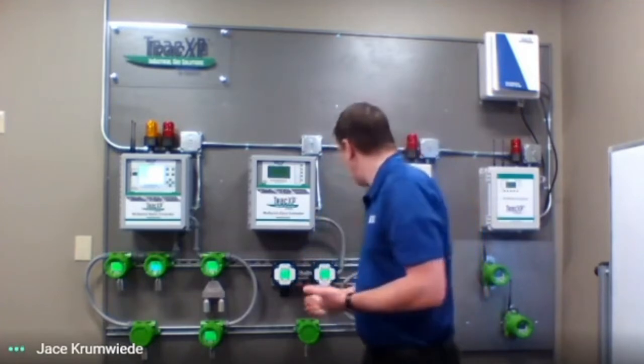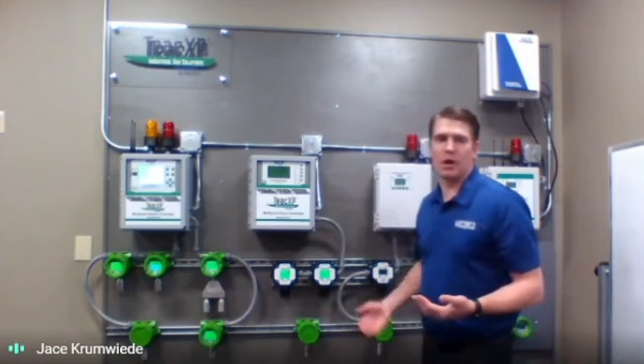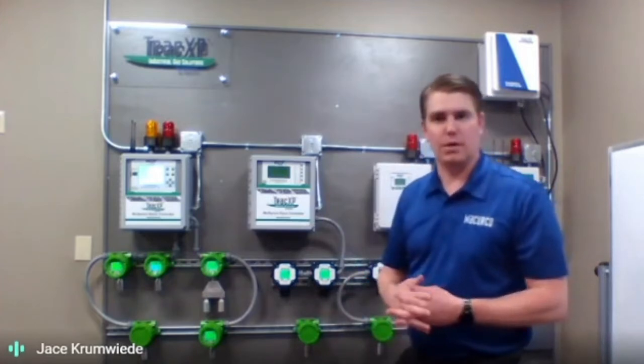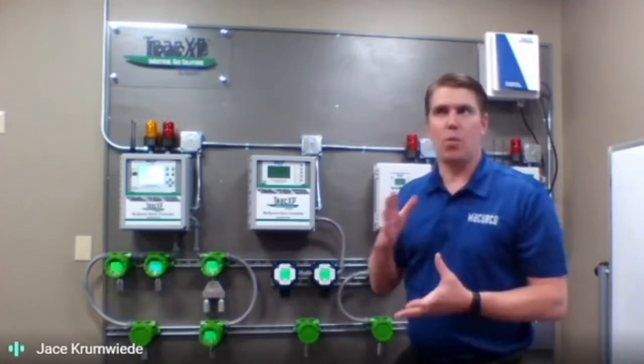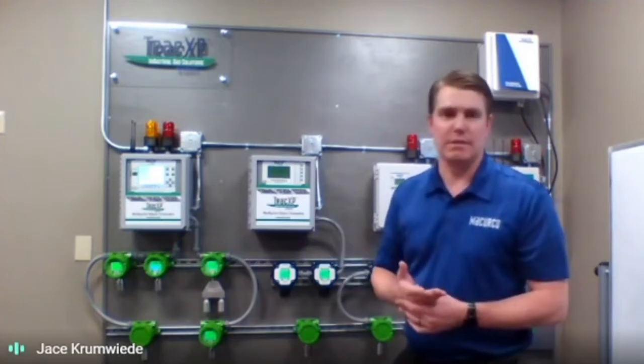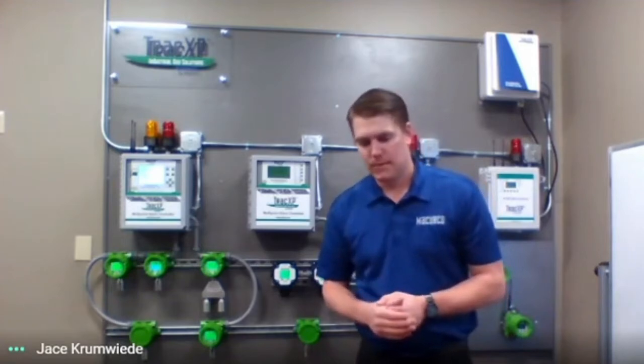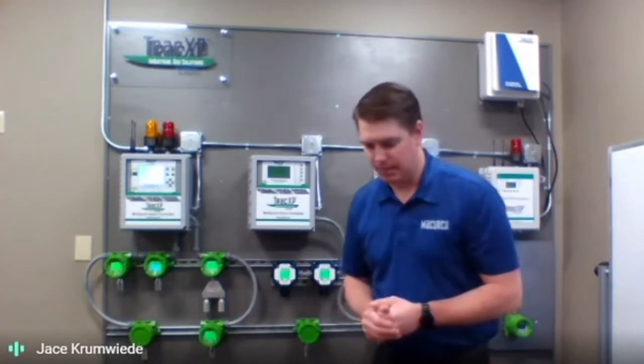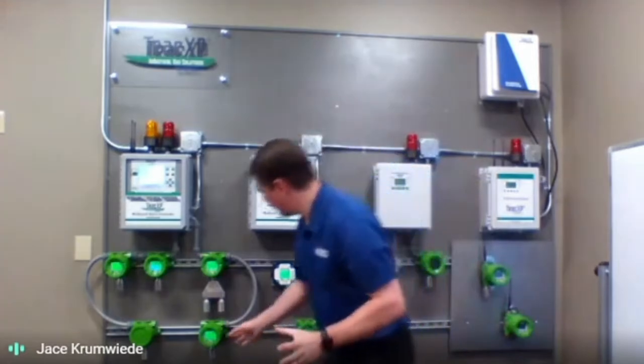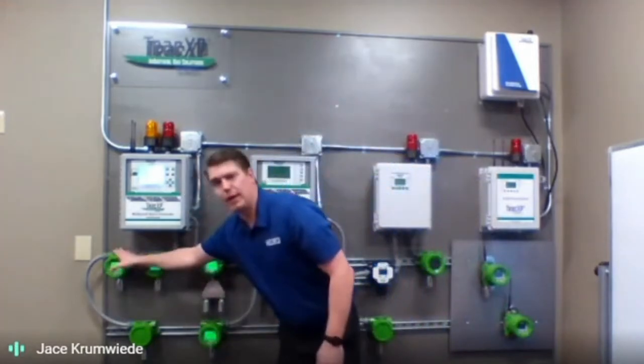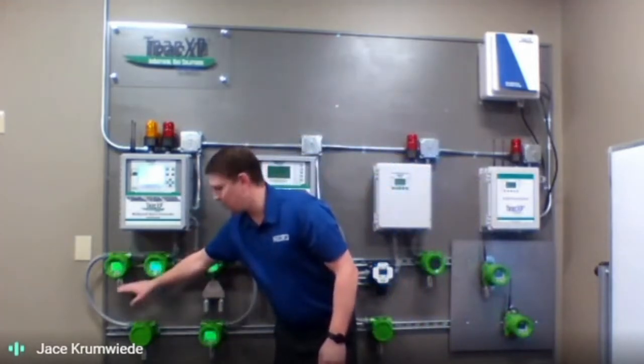Our other fixed transmitter, which is a non-color display, is still backlit, and you're going to have some limited options. So, start with the T40. One of the other great features of the T40 is that it is dual sensor capable of any gas type. So if you need two combustible gas sensors or two electrochemical, you can do that with the T40. Absolutely.